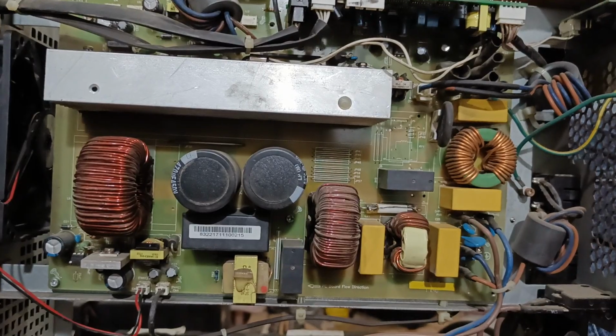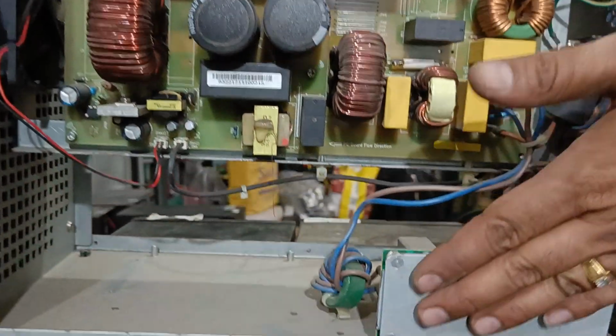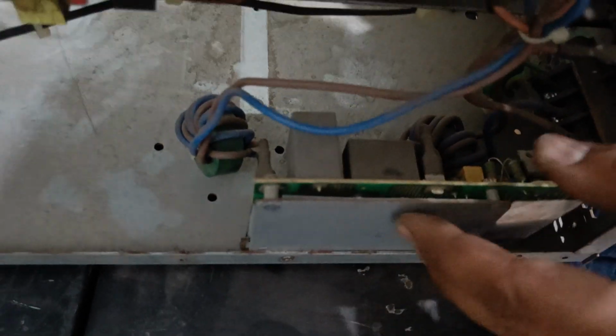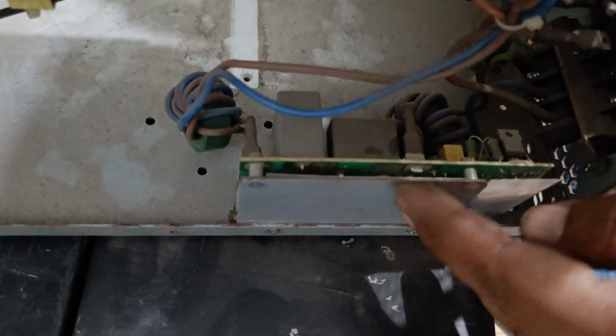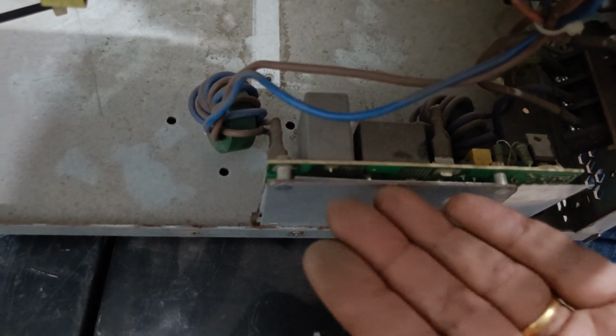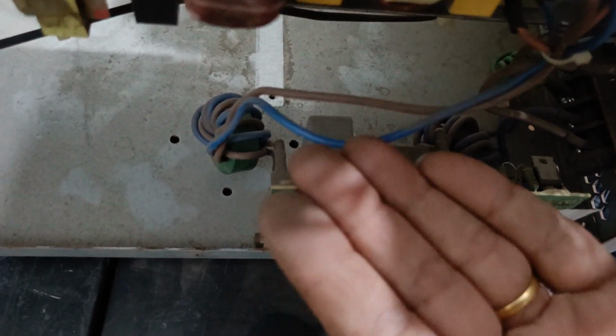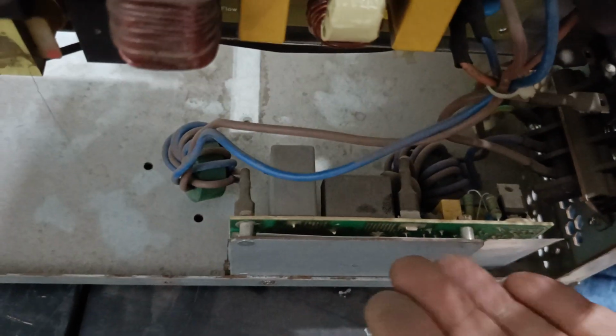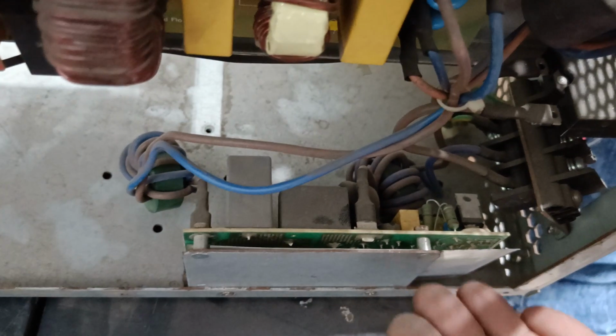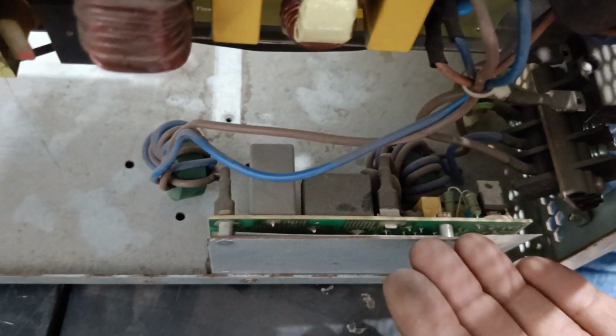So this is an OVCD card, over voltage cutoff device. It protects the UPS from input voltage issues. If the input voltage is very low, it will put the UPS on battery mode. If the input voltage is very high, it will also disconnect the input voltage and put the UPS on battery mode.